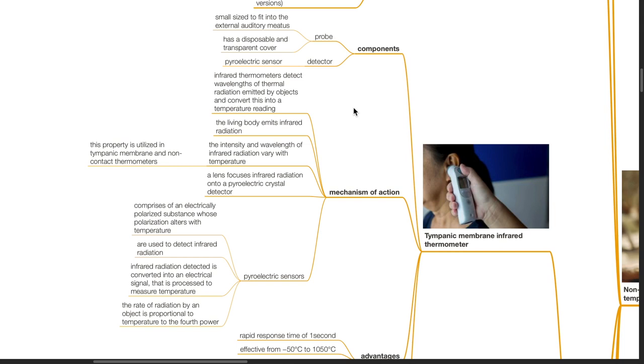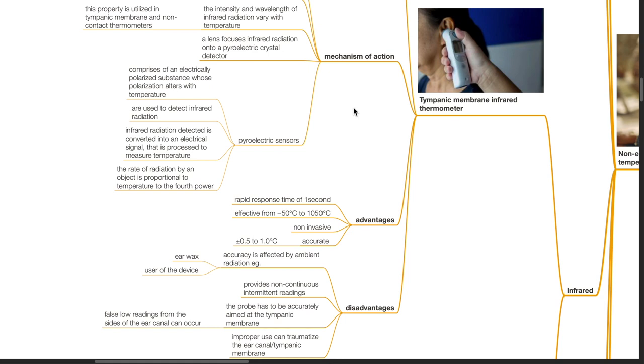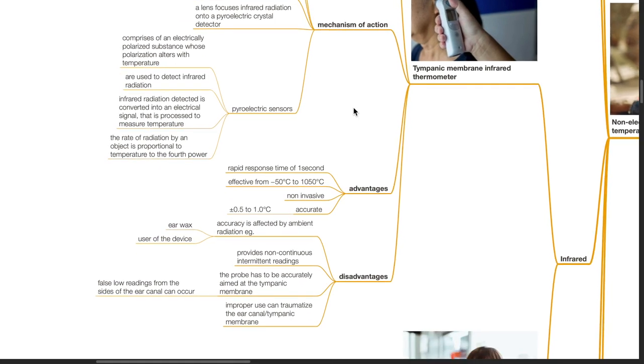The rate of radiation by an object is proportional to temperature to the fourth power. Advantages: rapid response time of one second, effective from negative 50 to 1,050 degrees Celsius, non-invasive and accurate to plus or minus 0.5 to 1 degree Celsius. Disadvantages: accuracy is affected by ambient radiation, which may be due to earwax or the user of the device. Infrared thermometers provide non-continuous intermittent readings. The probe has to be accurately aimed at the target or false low readings can occur. Improper use can traumatize the ear canal or tympanic membrane.